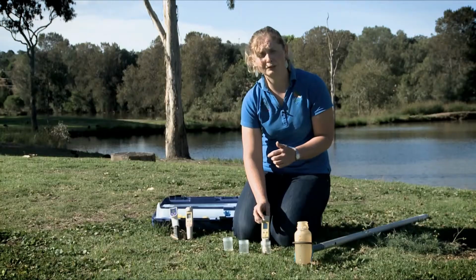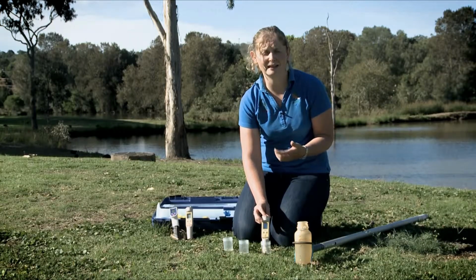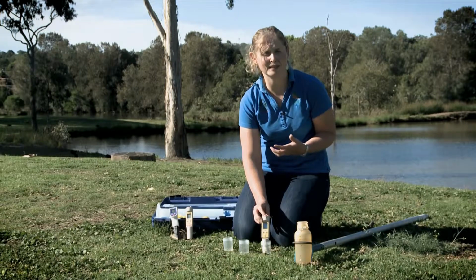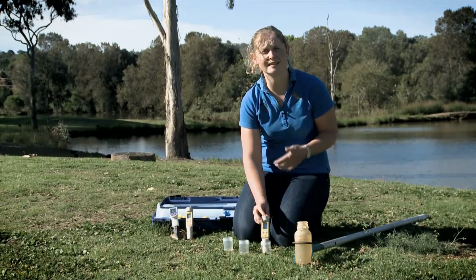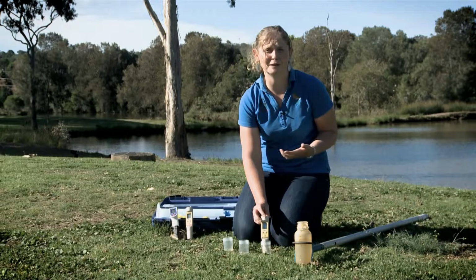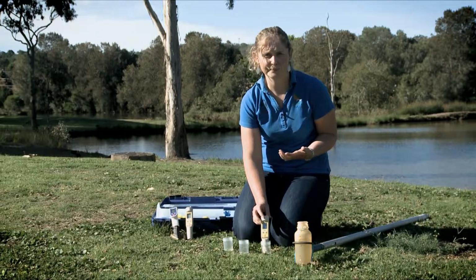With a dissolved oxygen meter, you do want to take the reading as soon as possible, maybe after 5 or 10 seconds, because the oxygen does get used up by the probe and it will affect your reading if you leave it for too long.